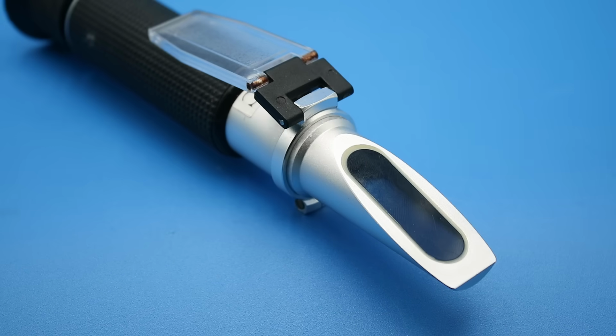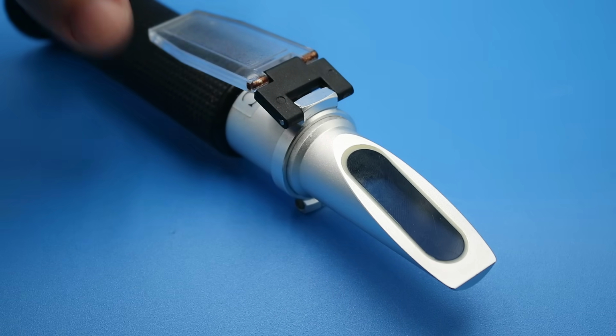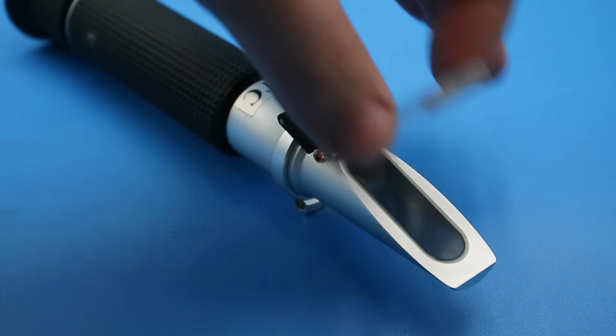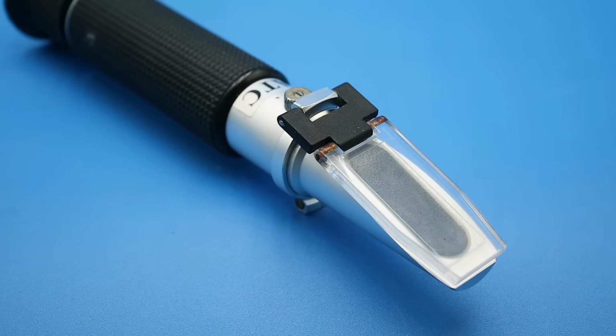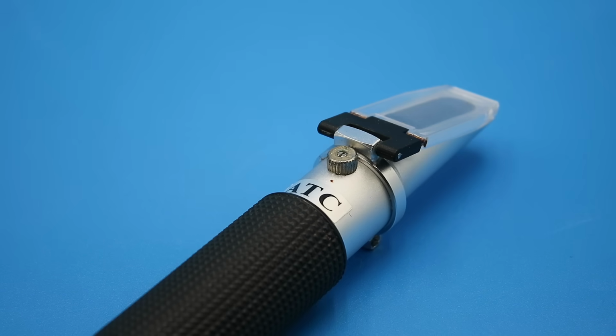Up at the front, we have our measuring prism fitted with a filter to narrow down the measurement wavelength. Most refractometers use yellow light at around 589 nanometers, but this model uses a blue light filter, likely around 480 nanometers. Over this, we have a hinged illuminating flap, which, as you can see, has a roughened texture to allow light to enter at various angles. Behind this is a little adjustment screw that allows the refractometer to be calibrated.